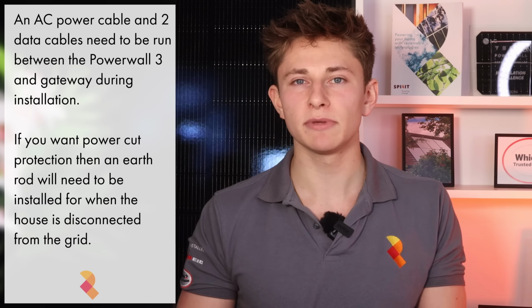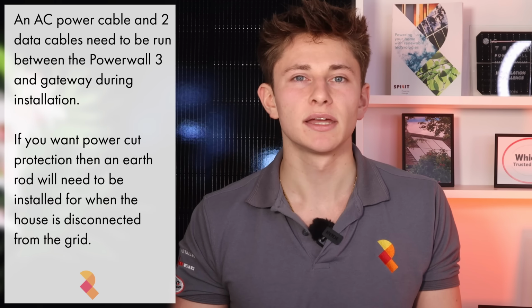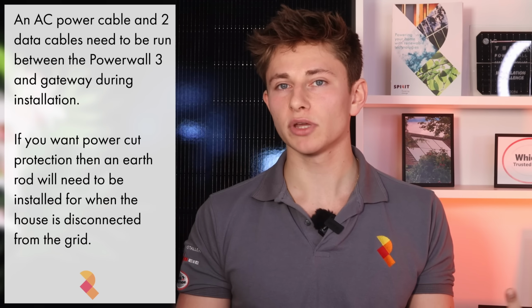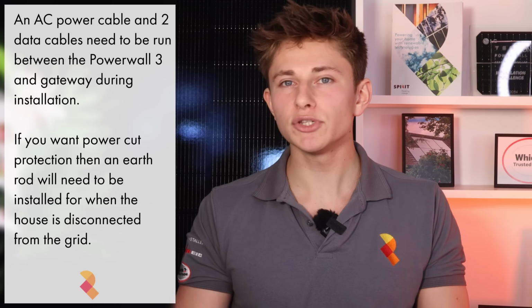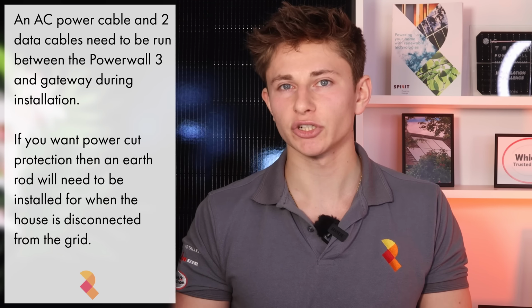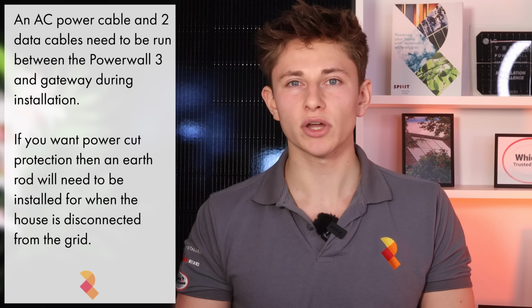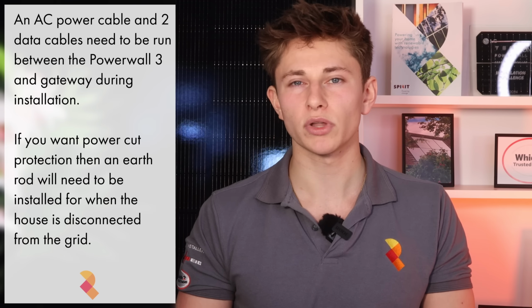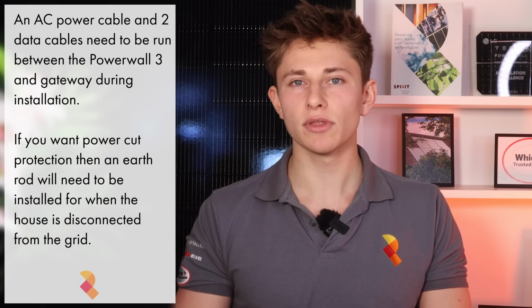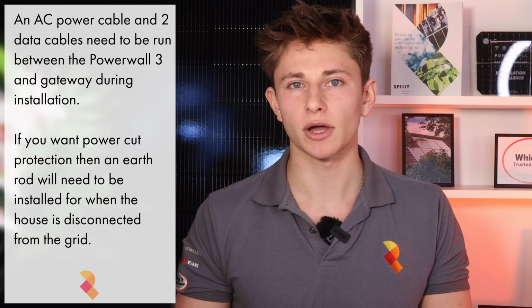There are 3 cables that need to be run from the Powerwall 3 to the gateway, an AC power cable and 2 communication cables. If you do have a gateway installed with power cut protection, your installer will also need to knock an earth rod into the ground if there isn't one at the house already. This is so that the system is earthed in the event of a power cut.